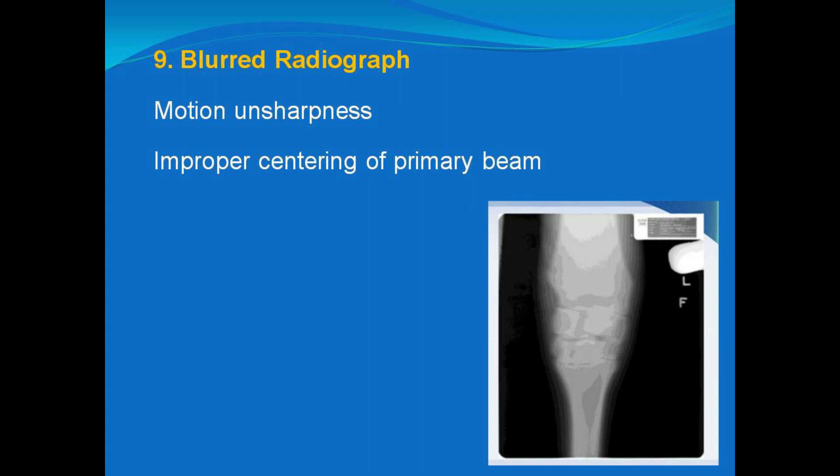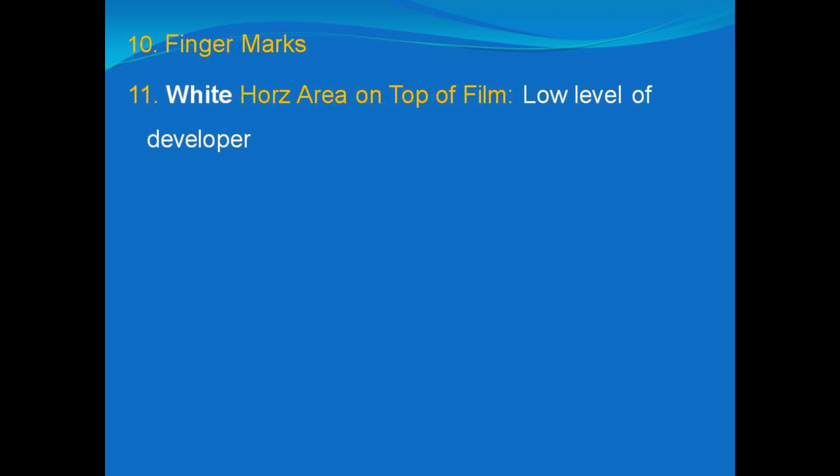The next problem is a blurred radiograph, which is particularly the result of motion unsharpness — when we are getting the radiograph, the tube head, the patient, or the table may move. It can also be due to improper centering of the primary beam, meaning the beam may not be centered at a 90-degree angle from the object being radiographed.